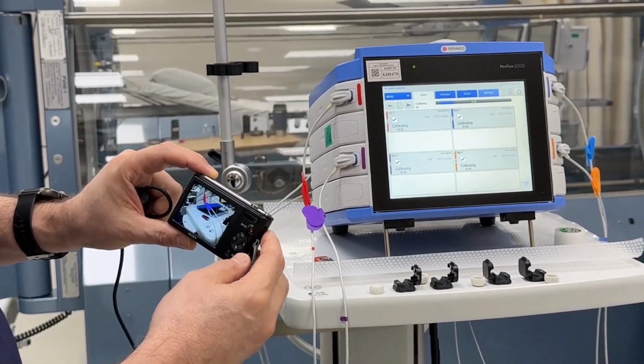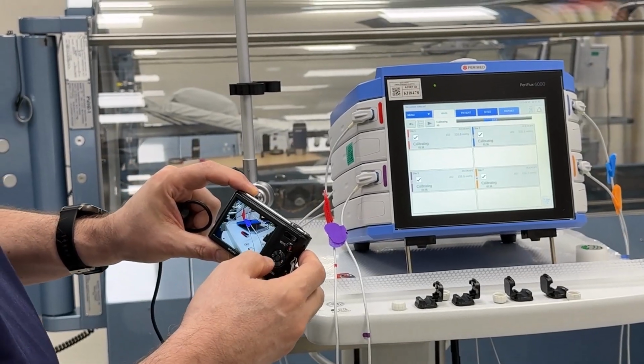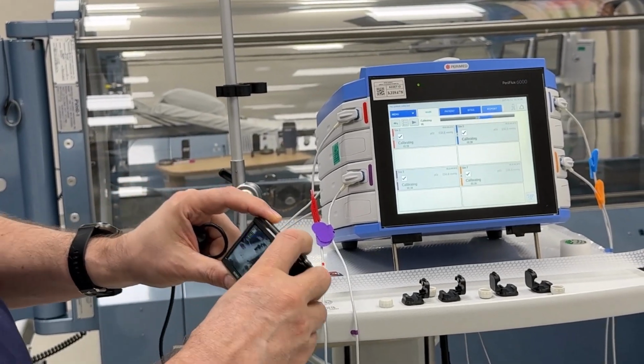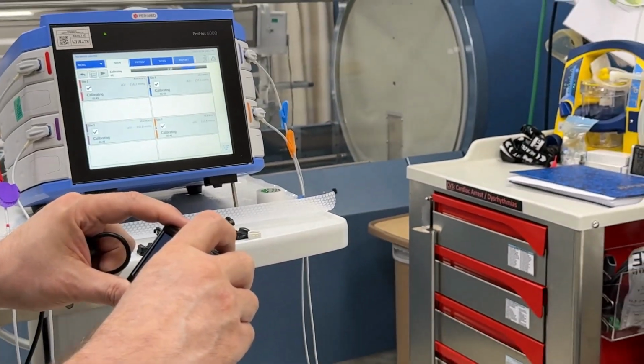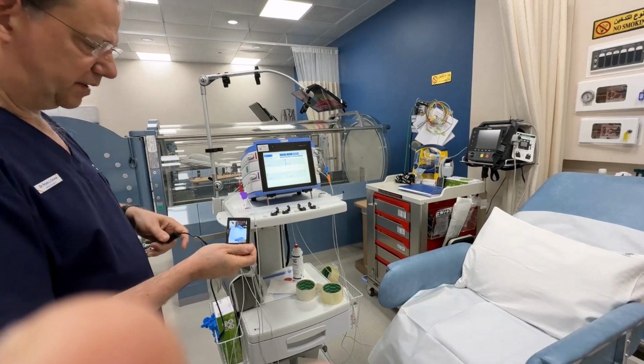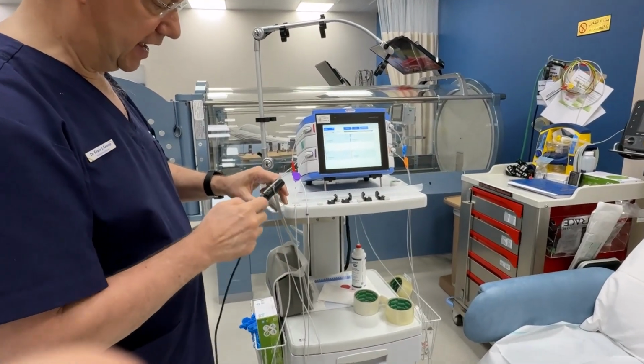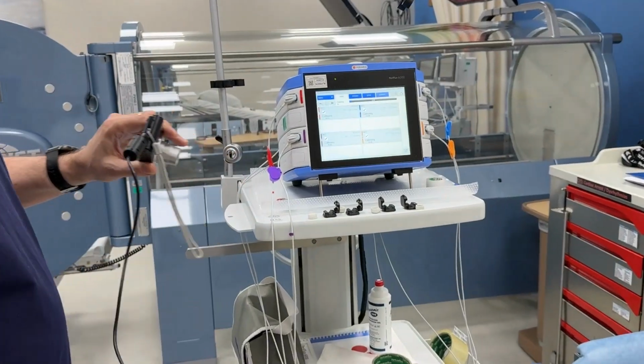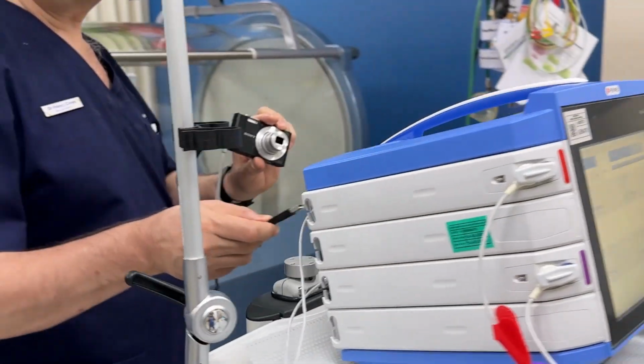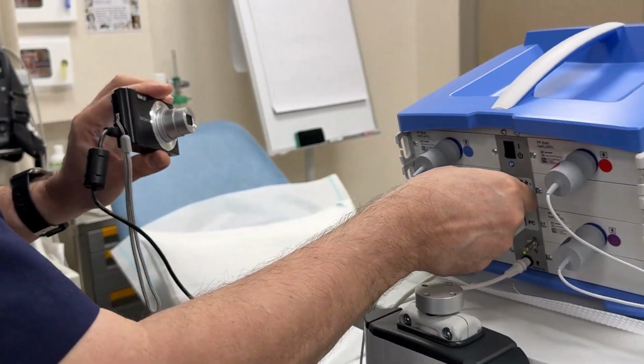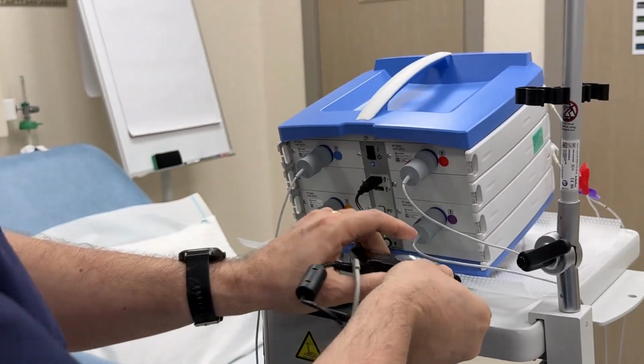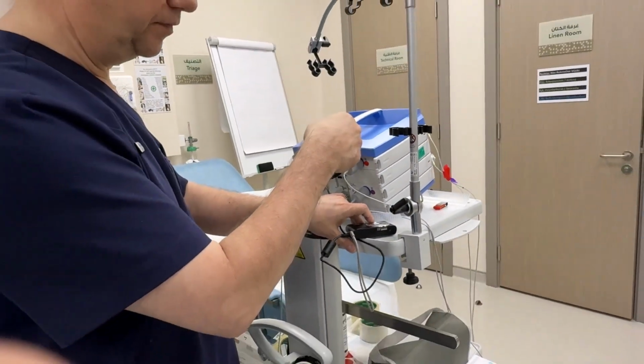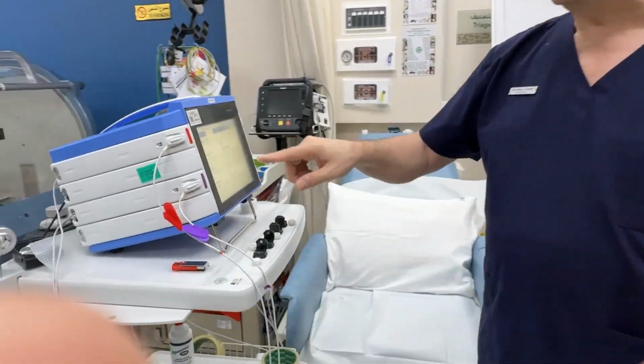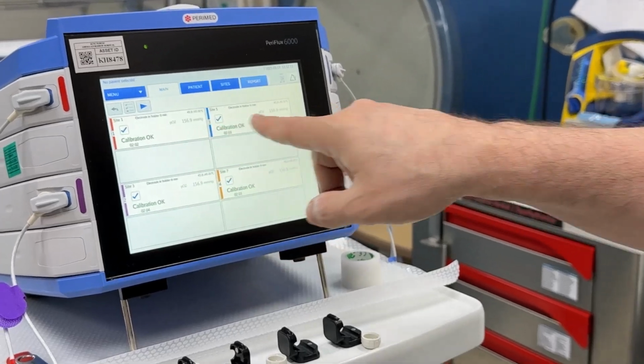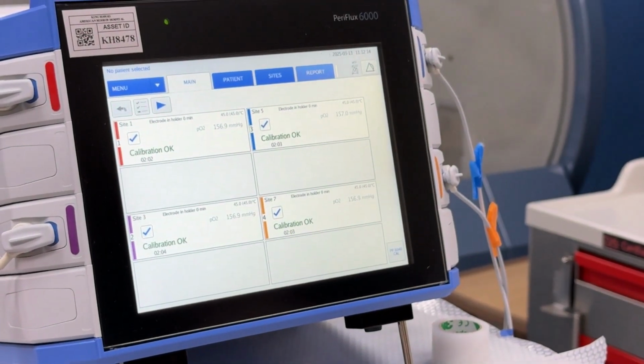The camera doesn't have a flash drive inside. It just uses the mass memory of the device. You take a picture of the wound, and then the camera needs to be connected to a cable. As I mentioned, it needs to be put in that first slot at the back of the machine. What will happen now is the camera will close, and you hear a beep, which means that the camera has been recognized. In the meantime, the calibration has completed and all 4 sensors have been calibrated okay.